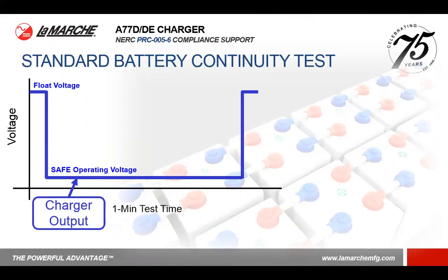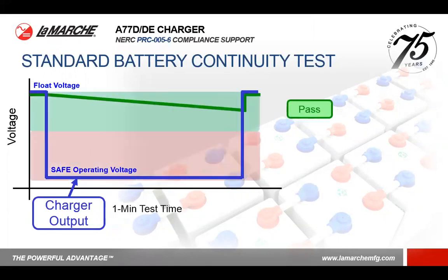But because the battery is in parallel with the load and the charger output, as the battery charger output drops, now it's going to take over the share of handling the load, which would be the station standing load during the 1-minute test time. So over this 1-minute period, if the battery voltage only falls a short amount, we're going to pass that battery as being healthy. If it dips into the red zone, we're going to identify it as a check battery system.